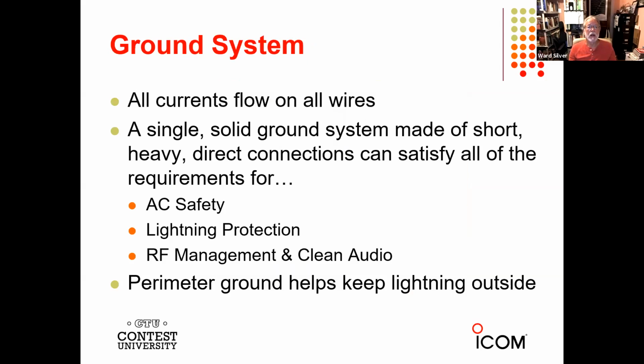And finally, your ground system, all currents flow on all wires. So your AC fault current is going to flow on all wires. Your lightning is going to flow on all the wires. It doesn't separate. AC doesn't go, oh, I can't flow on that. That's not a green wire. Nope, it'll flow on everything. So the point is that a single solid ground system of short, heavy direct connections satisfies all of the requirements we've been talking about: AC safety, lightning protection, RF management, and clean audio. And that perimeter ground keeps Mr. Lightning outside. This is an overall schematic.